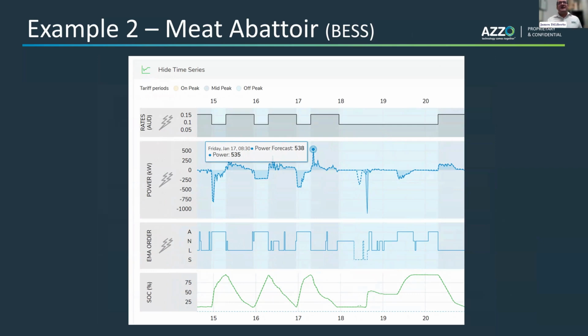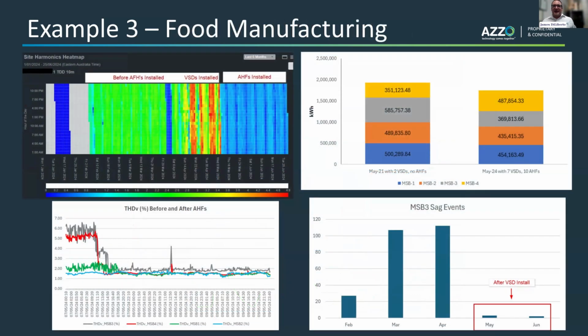Great example. Another example, food manufacturing. This is where the introduction of energy efficiency opportunities like variable speed drives to manage starters actually created some challenges with harmonics, which could then be addressed by active harmonic filters. The bottom line is, the challenges coming from their own transformers manifesting in voltage sag events were mitigated significantly by again installing technology.